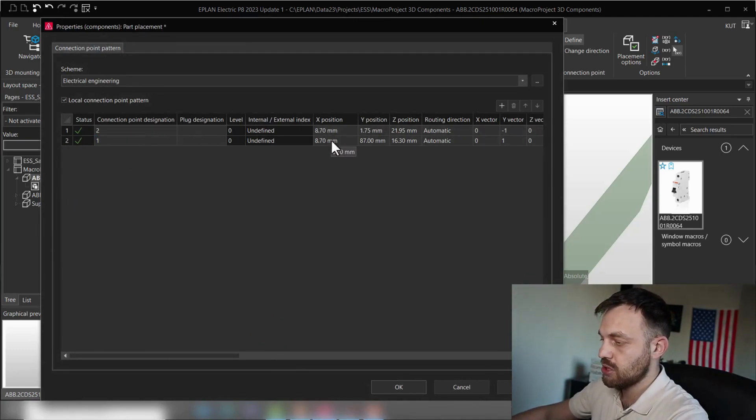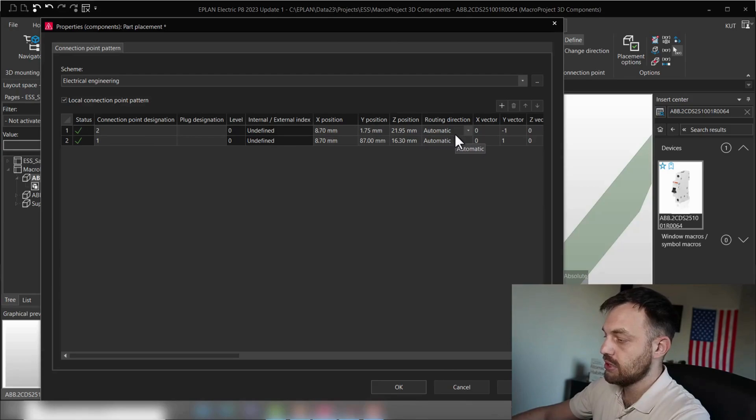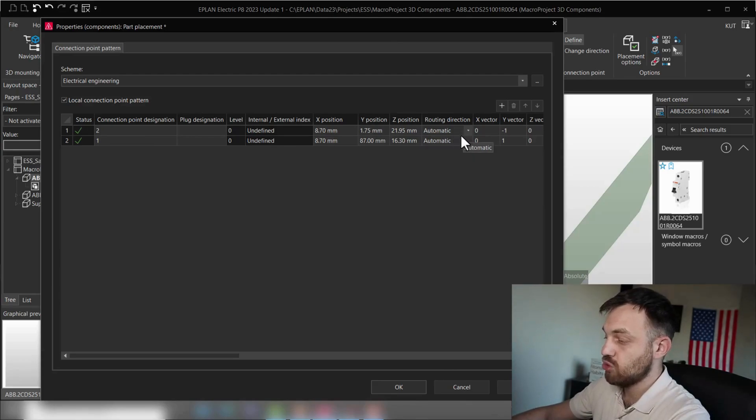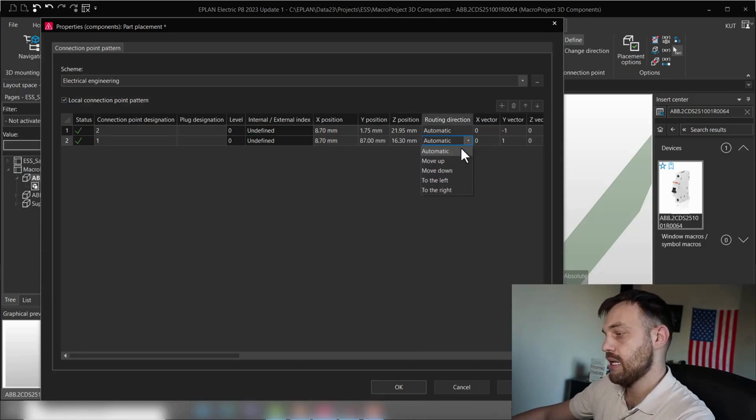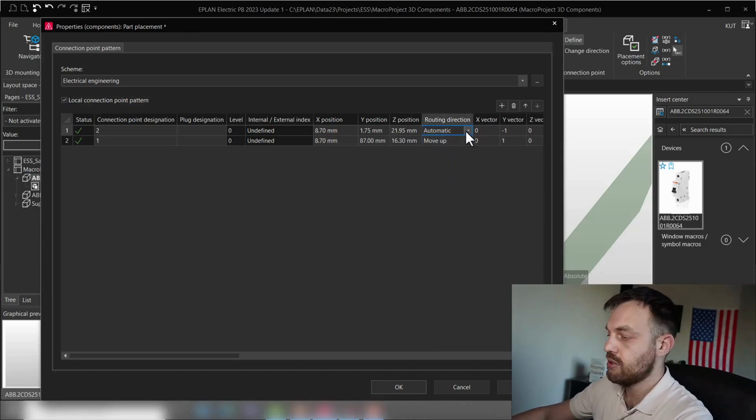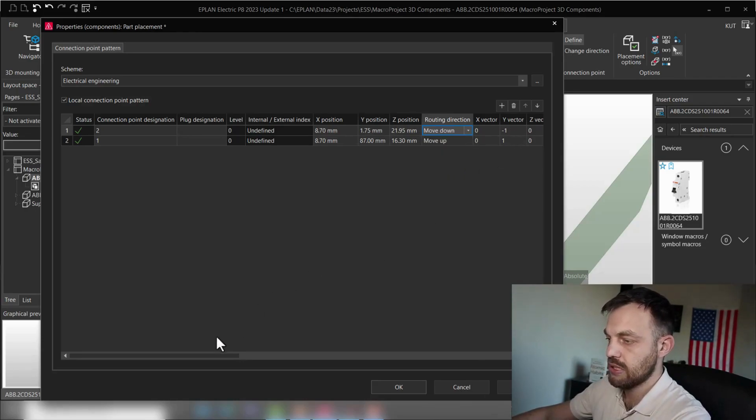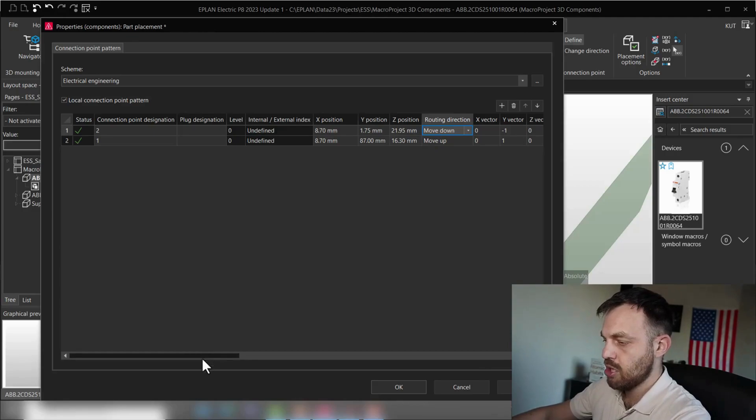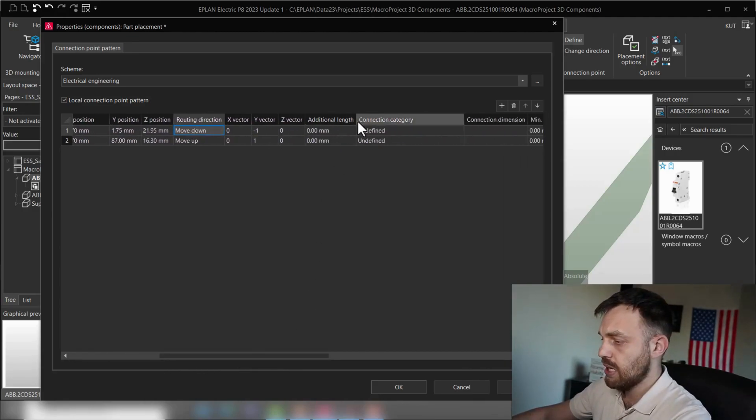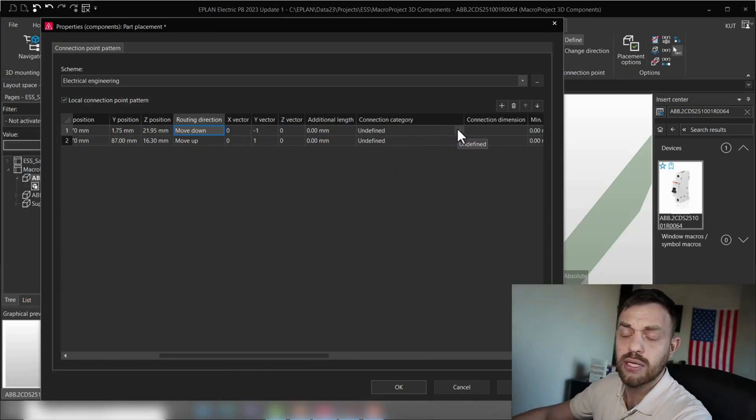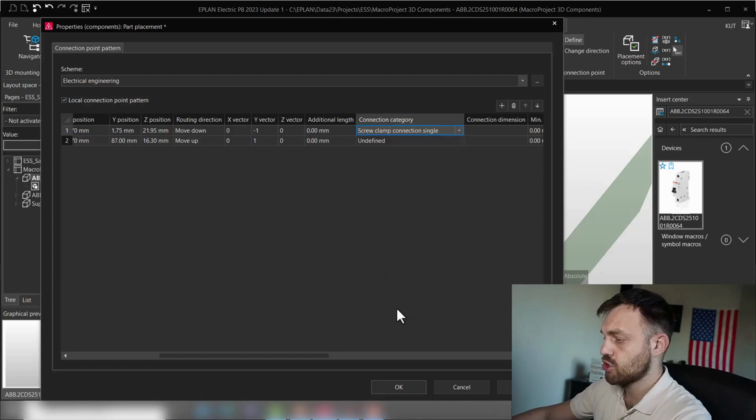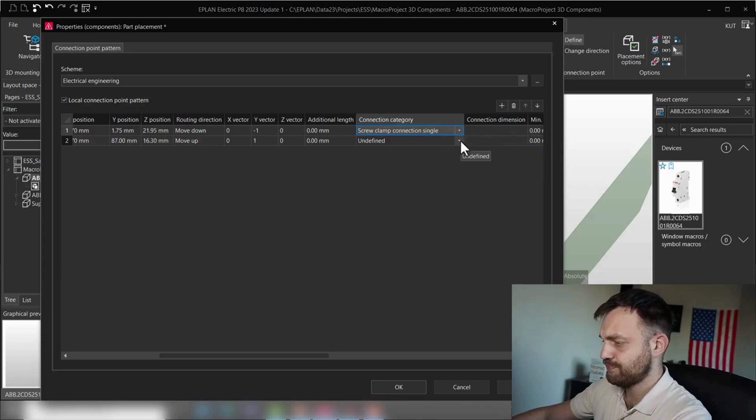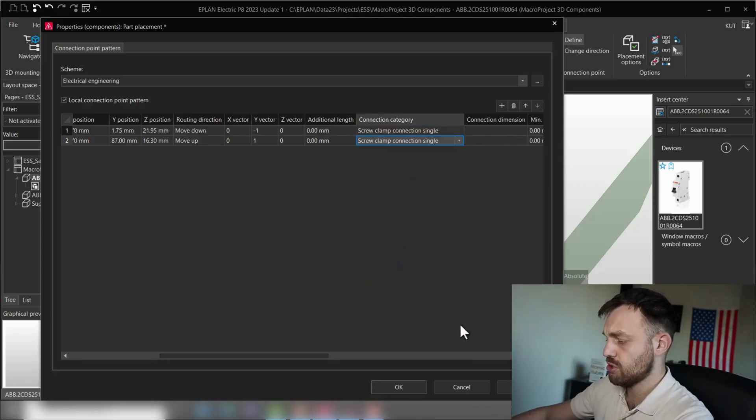So as you see, the X position is the same. The Y position differs. And the Z position, in this case, also differs. The routing direction is automatic. I will recommend you here, since this is going up, to say move up. And here, the routing direction moved down. The vector is obviously opposite directions. What I will also recommend you to do is to add here the connection category, which is screw clamp connection single and screw clamp connection single.